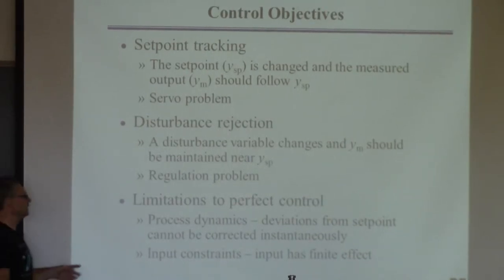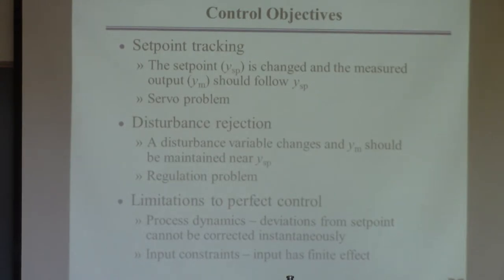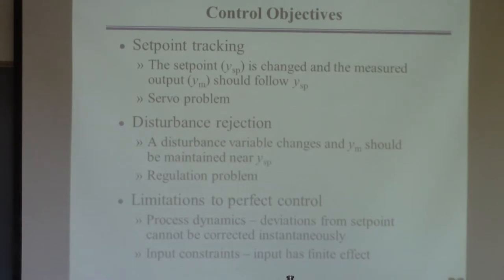There are limits to how well you can do with control. If you want a 25% increase in production, you can't get the production rate there instantaneously, because the plant has so many dynamics associated with it. The dynamics of a distillation column are so slow that going from one operating point to another takes well over an hour. It's a function of the inherent dynamics of the process — you just have to live with that. You can't make a process with a time constant of an hour respond in seconds.